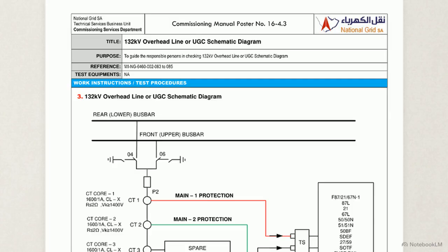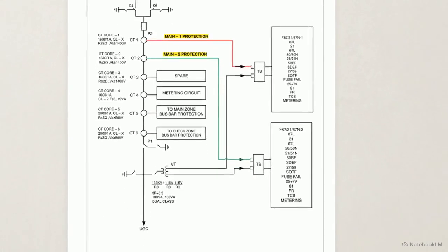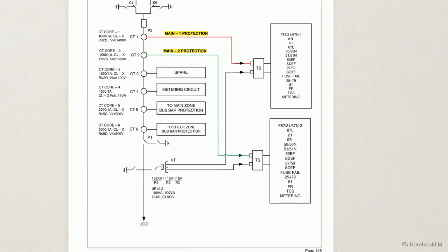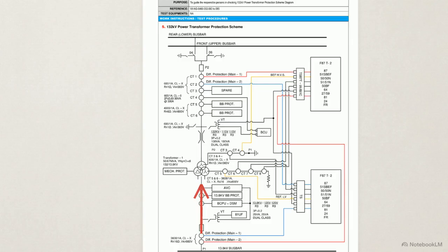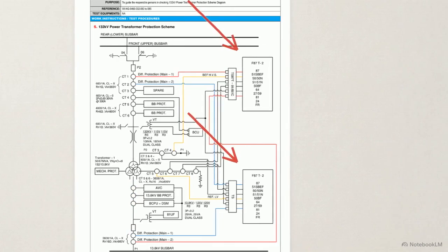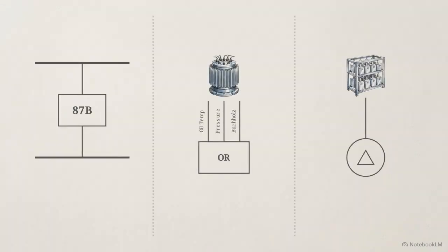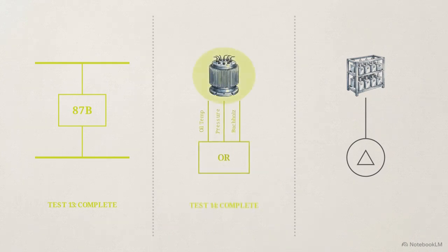Shifting to the 132 kV infrastructure, this diagram for the overhead line and underground cable circuits highlights the dual protection strategy, showing the main 1 and main 2 protection paths feeding into the relay blocks. This schematic traces the 132 kV power transformer differential protection paths, mapping the complex wiring that terminates at the relays to ensure transformer stability. We repeat this rigorous tracing for the 132 kV busbar check zones, shunt reactor auxiliary alarms, and capacitor bank unbalanced protection circuits, driving toward the completion of tests 13, 14, and 15.